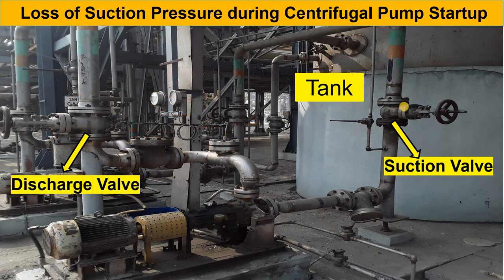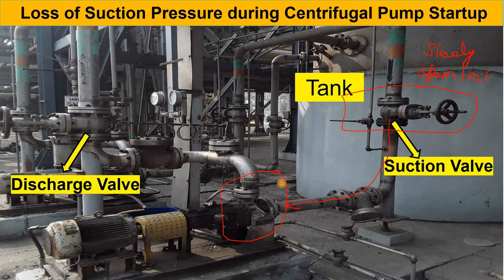Now, how do you operate the centrifugal pump during startup? First of all, you will open the suction valve completely — 100% — slowly. Your fluid will flow from the tank through to the pump. Then you start the pump, either from the LCS or from the DCS. Once started, the PG will show a reading. Monitor the pressure, and then open or throttle the discharge valve slowly.